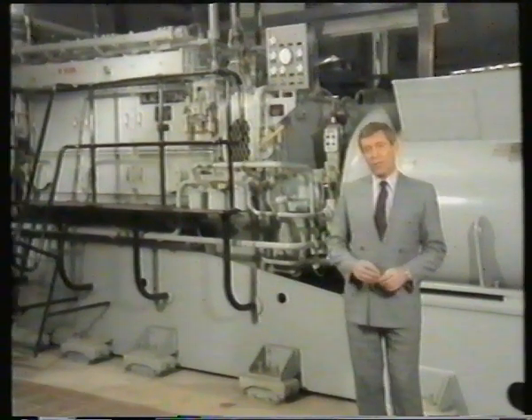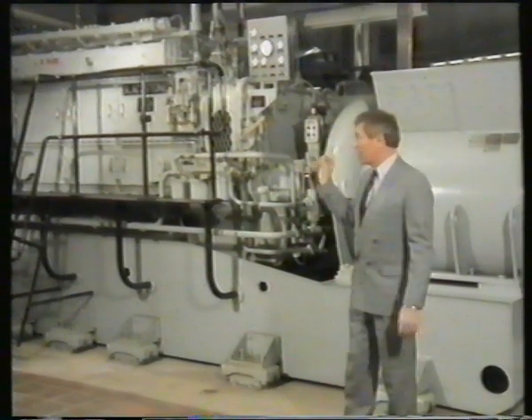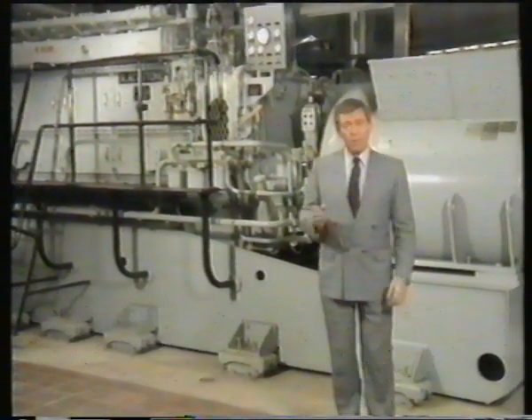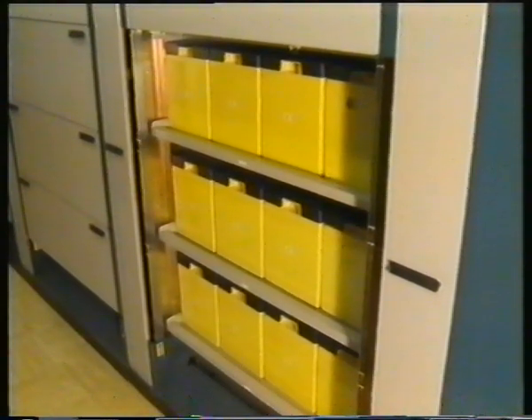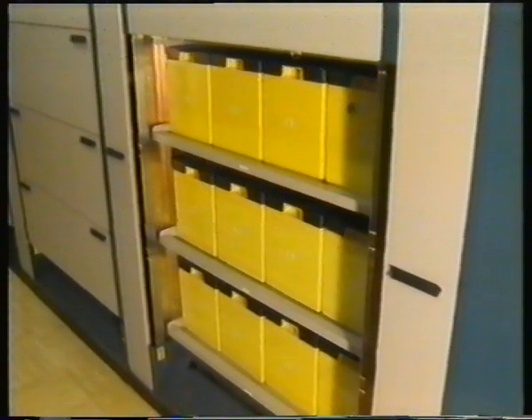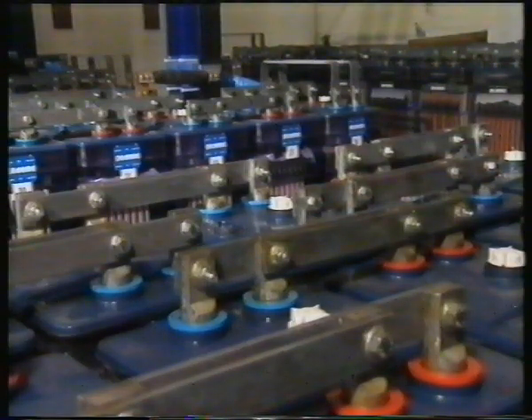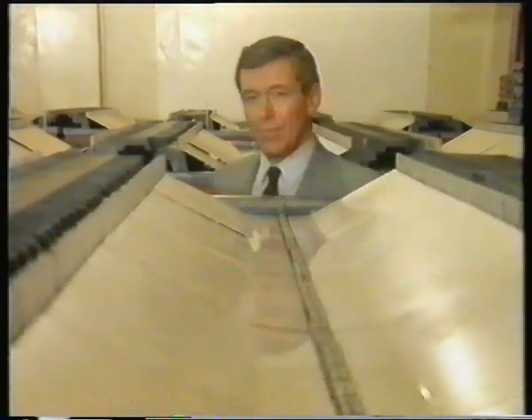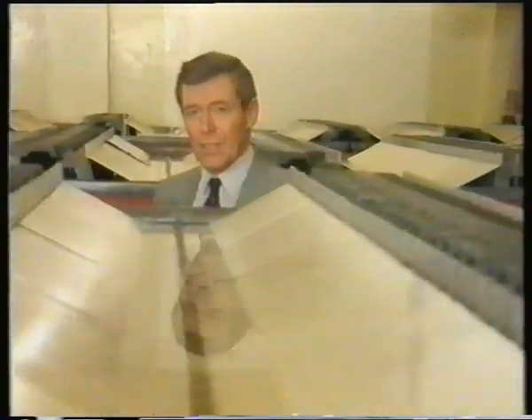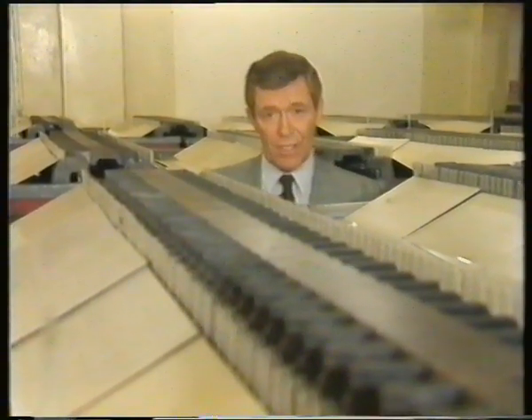This supply is converted from the mains, but in the case of a mains failure, a standby generator like this will automatically start up and take over. As a last resort, if the standby generator also fails, power is supplied for a limited period by rack-mounted batteries within the equipment area itself, or from a dedicated battery room such as this, or this. What this does mean, however, is that most areas of an exchange cannot easily be electrically isolated. In other words, don't assume if mains power has been cut that a zero-volt situation exists.